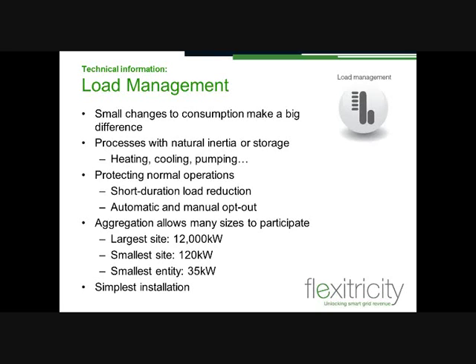It doesn't all have to be generation. Load reduction, or load management — delivering load reductions for short periods when the national electricity system or the local electricity network hits a period of stress — is just as valid. What we ensure is that any load reduction asset participating with us does so only within the constraints of keeping up the quality of core business operations. For example, a cold store participating in demand response: if the temperatures within that cold store were at a level where a demand response event would threaten the quality of service to its customers, under our system that cold store would automatically opt itself out of demand response. Site staff also have the ability to manually opt out.